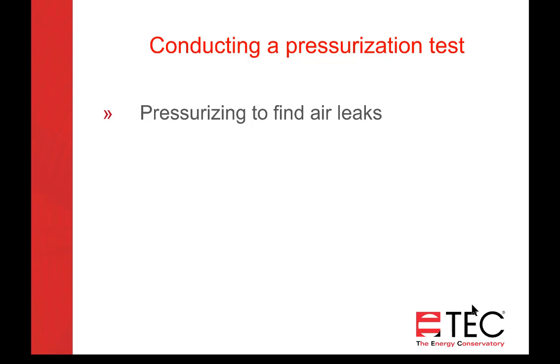We used to have a standard when I was doing blower door testing, if you're doing an inspection on some weatherization work that was done on tongue and groove paneling, for example, we would pressurize the house to 25 pascals. And if it would pull smoke from an inch away, so it would hold the smoke puffer an inch away, if you could see that smoke travel from the smoke puffer to the leak, then that was a fail. And that was a pretty good test.